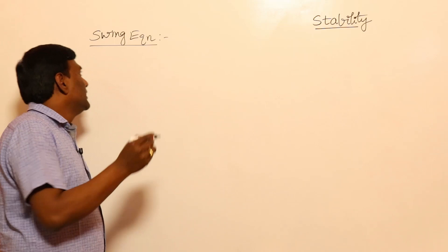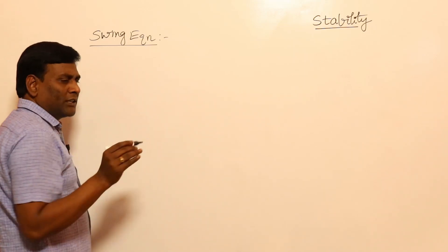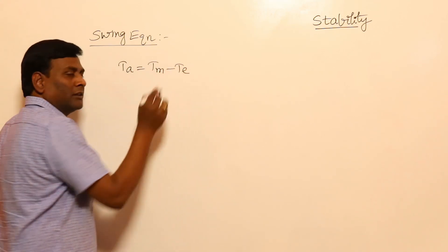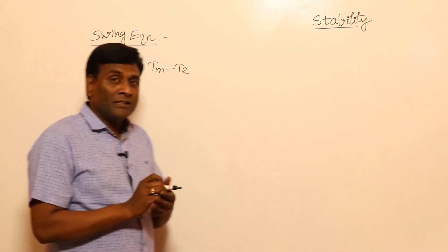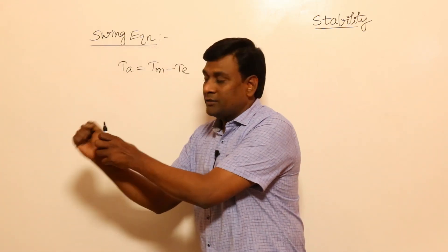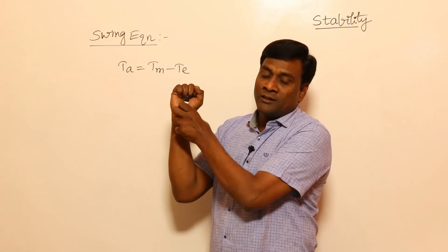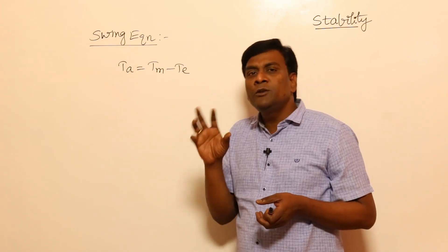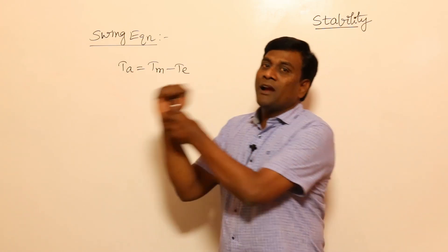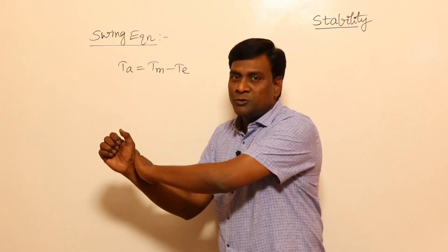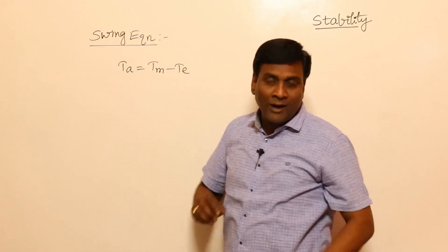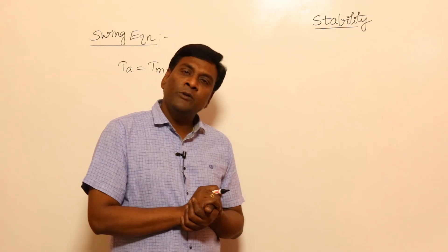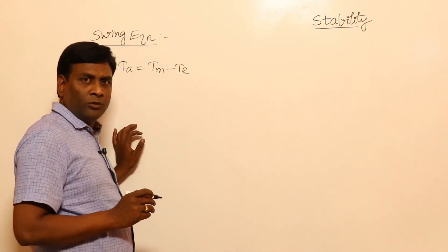The accelerating torque equals mechanical torque minus electrical torque. If mechanical torque equals electrical back torque, the system is stable and the rotor rotates continuously at synchronous speed without swinging. If mechanical torque is more than electrical back torque, there will be accelerating torque — which we already analyzed in a previous video.